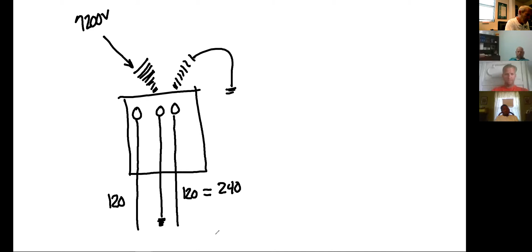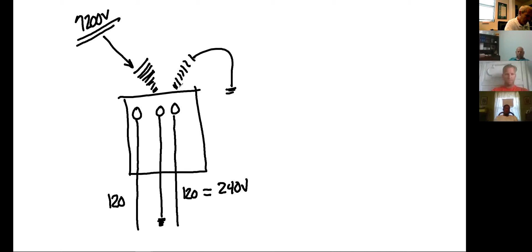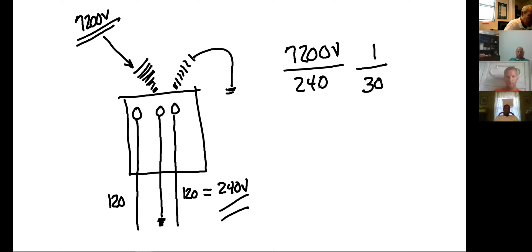So what are my two voltage numbers? 7,200. It's transformed to 240. So let's take 7,200 volts and divide it by 240. What is the answer? 30. So for every one of these, I have 30 of these. 30 times 240 equals 7,200. Everybody get that?